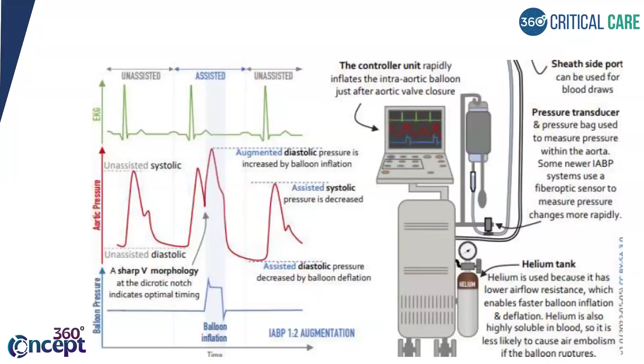So this is the rest of the tank. I told you, helium tank. We use helium. Why? Sometimes you can get questions about why helium is used. So helium is used because it's a less dense gas, so it can easily go in and come out. And even if there is any error and the balloon ruptures, helium is a very soluble gas, so it can easily get dissolved in the blood, and it doesn't form an air embolism. So there's no risk of air embolism even if the balloon ruptures, and it is a very, very less dense gas, so it can easily be inflated and deflated. The balloon inflation and deflation happens very fast. Okay, so that is why we use helium.